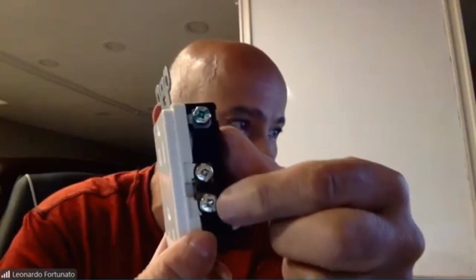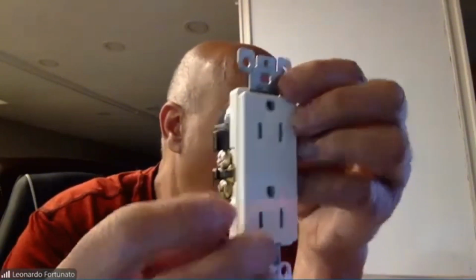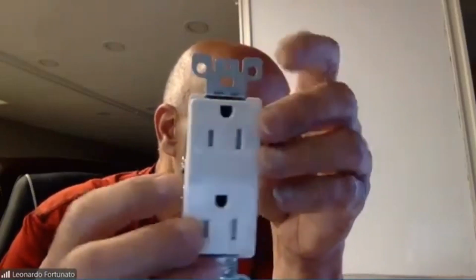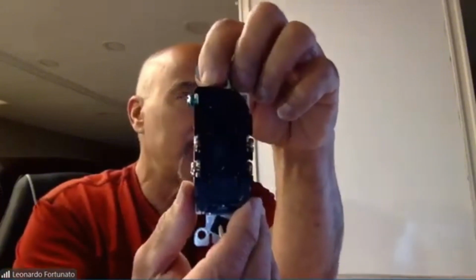In the last 30 years or so, the neutral slot is longer than the hot side. So this is the neutral, that is the hot. How did I know that without even looking at it from the front? As you can see, I'm on the back side of this receptacle. I can tell from the screws—the screws on the neutral side of my receptacle are silver, while the screws on the hot side are brass or copper colored. That's how I determine from the back which side is neutral and which is hot. Fair enough?